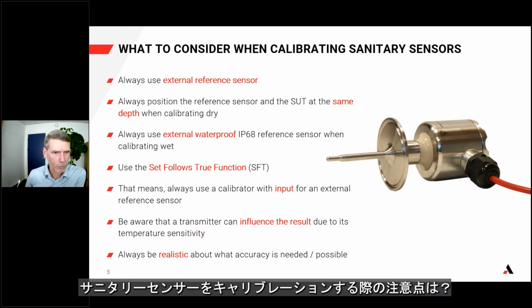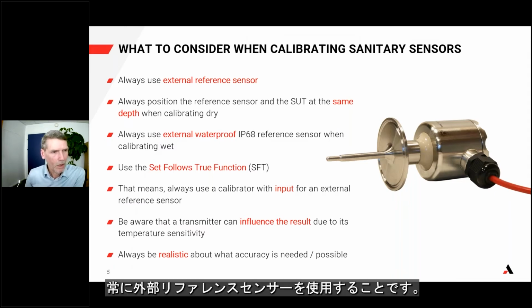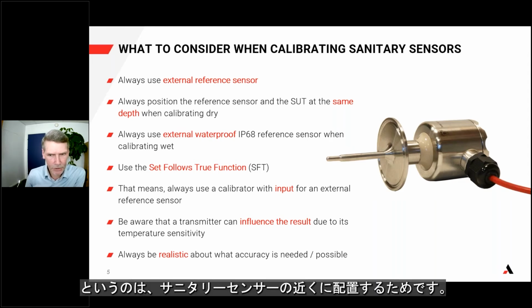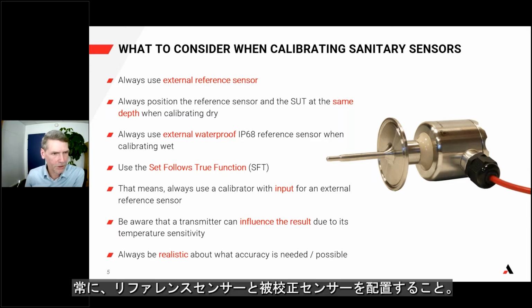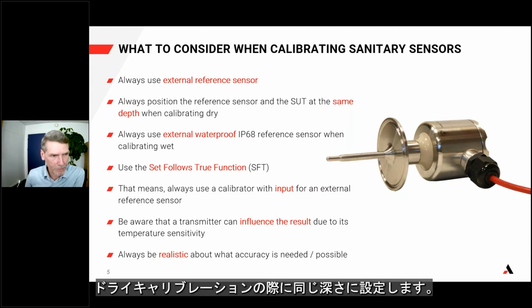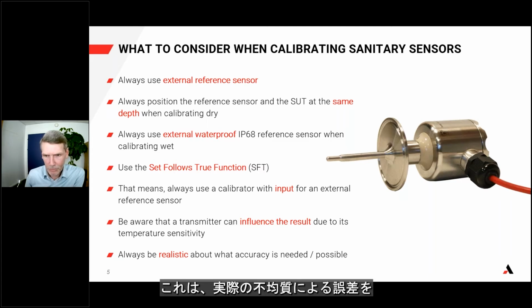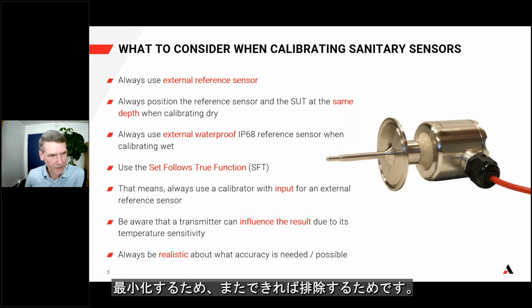What to consider when calibrating sanitary sensors? Well, always use an external reference sensor, and that is in order to have it positioned close to the sanitary sensor. Always position the reference sensor and the sensor under test at the same depth when calibrating dry. And this is in order to minimize, hopefully eliminate, error from axial inhomogeneity.